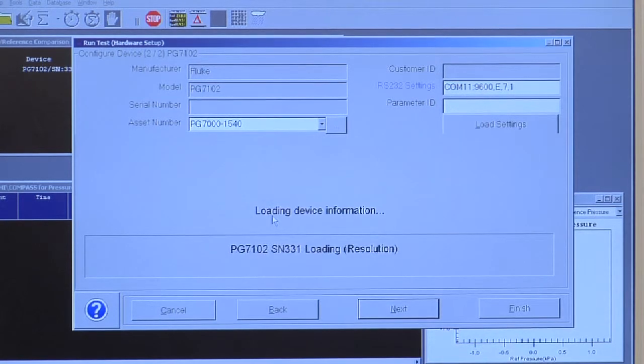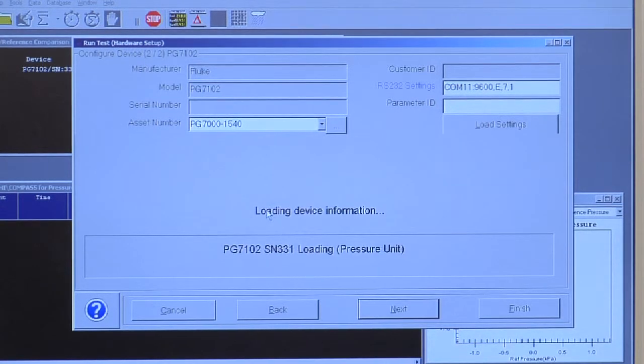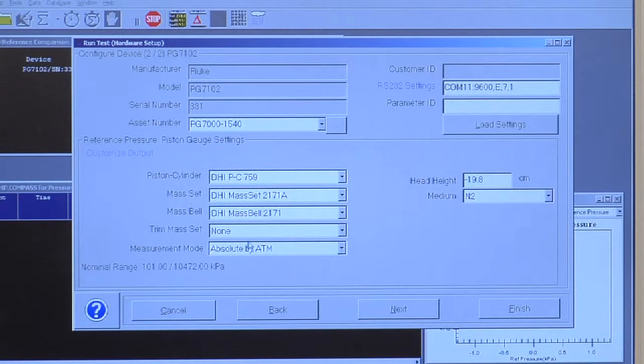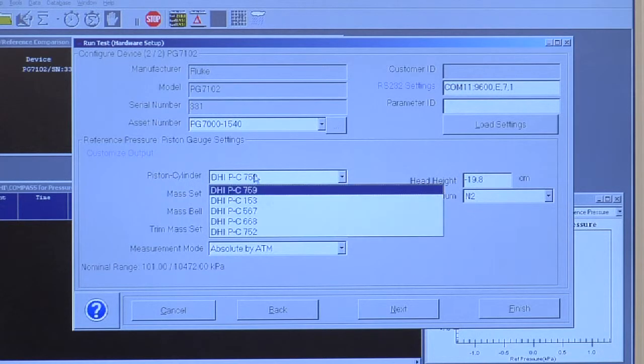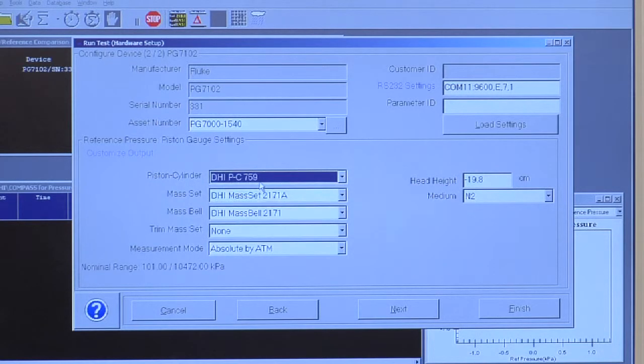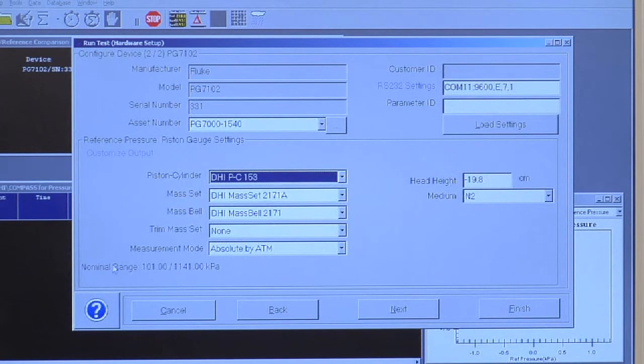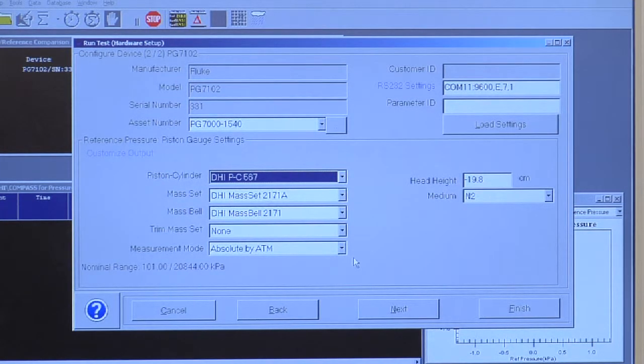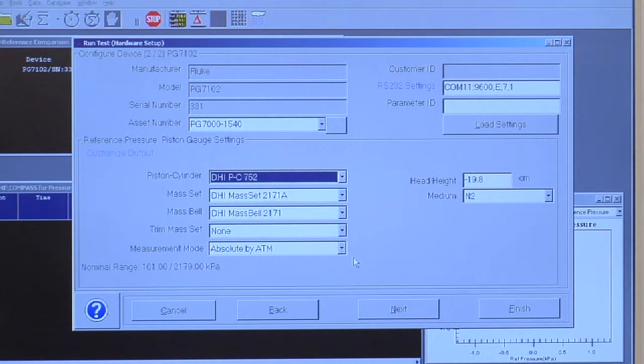Now I have to load my piston gauge settings. This is the piston cylinder I'm going to use. Notice as I change my piston cylinder selection, I get my nominal range. It helps simplify the verification of the proper piston cylinder.